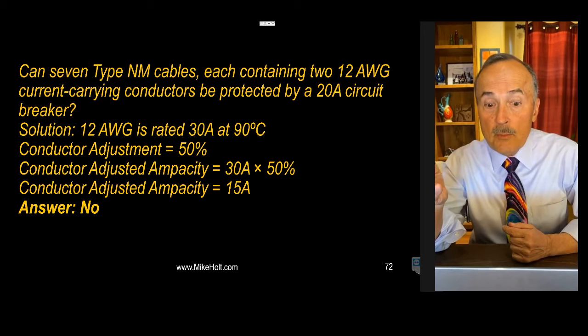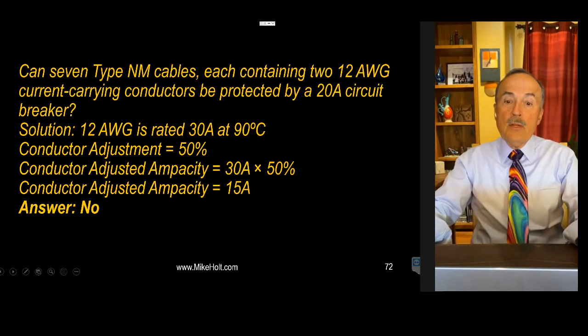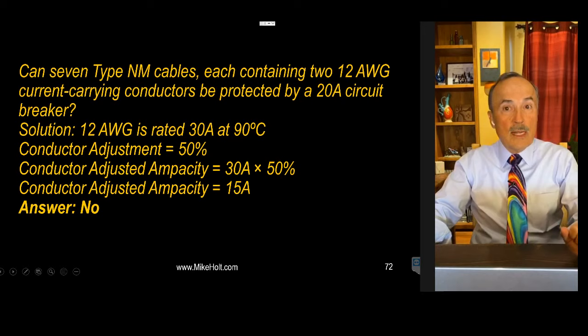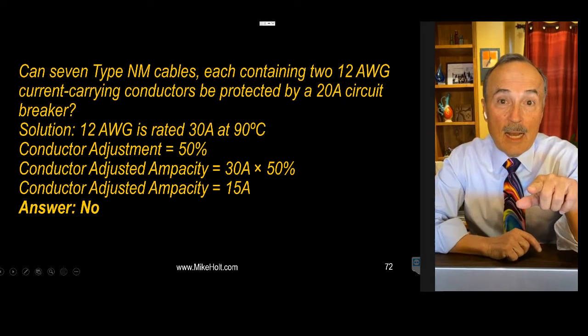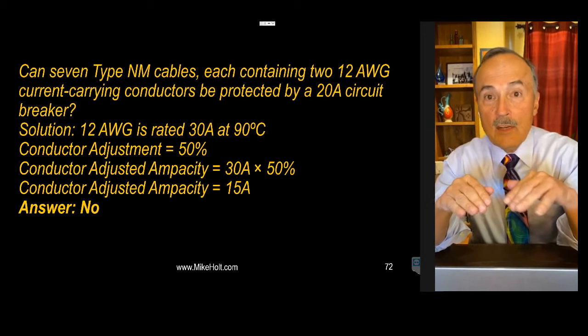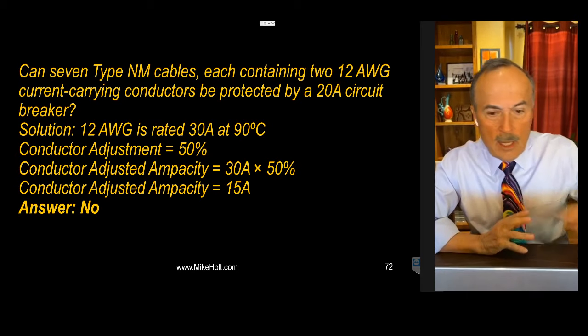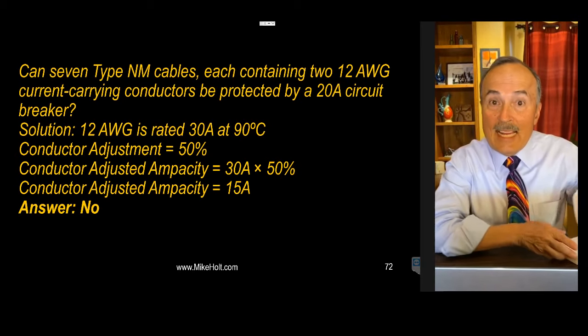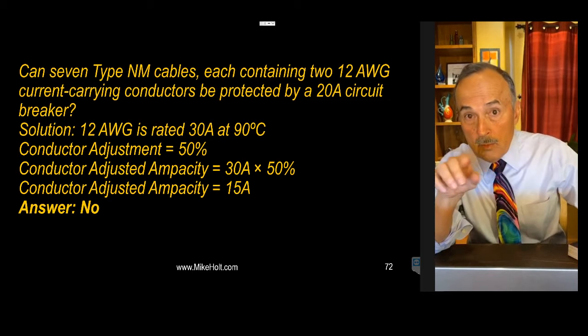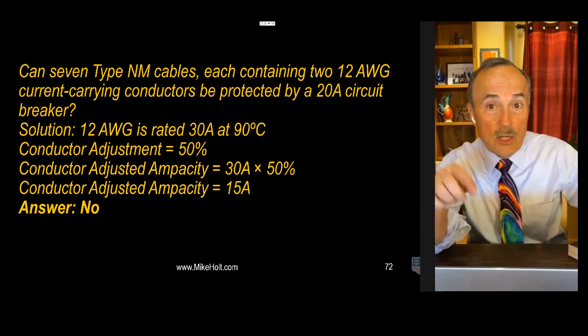Since we're adjusting the ampacity, we're going to go to table 310.16, and we're going to look it up, and we're going to find out 12 gauge wire is rated 30 amps. We saw the adjustment factor in the table, which is before table 310.16. It was going to be 50%, and 50% of 30 amp wire is 15 amp wire, so no, you cannot put it on a 20 amp circuit.